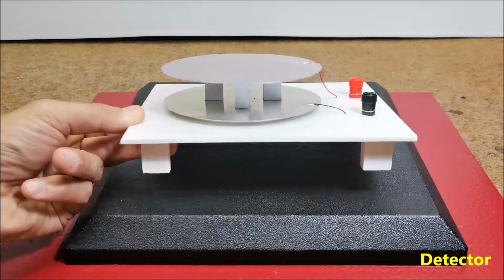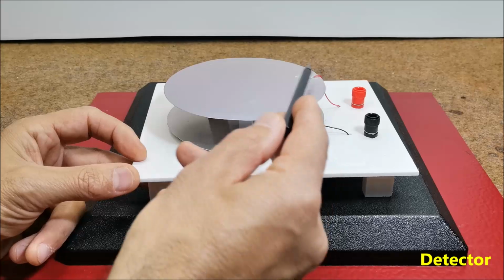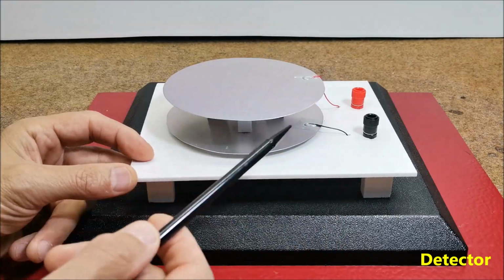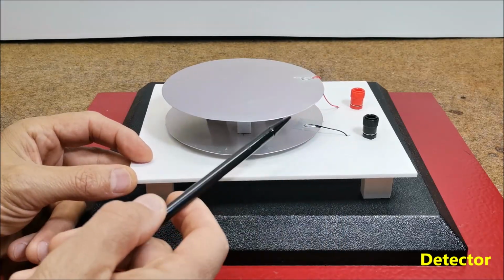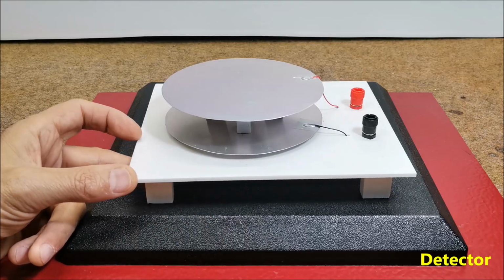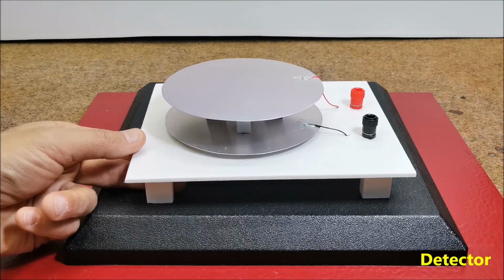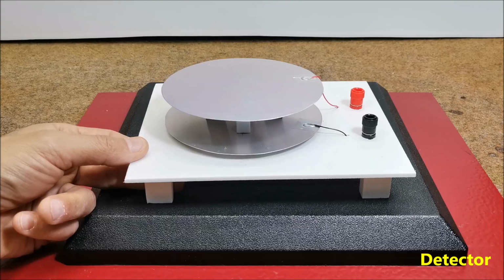The sensitivity of the detector is directly proportional to the surface area of the electrodes and inversely proportional to the distance. This means that the larger the surface area and the smaller the distance from each other, the greater the sensitivity.